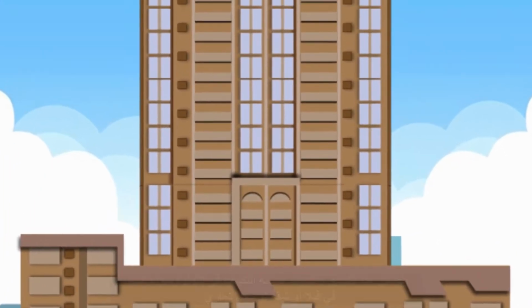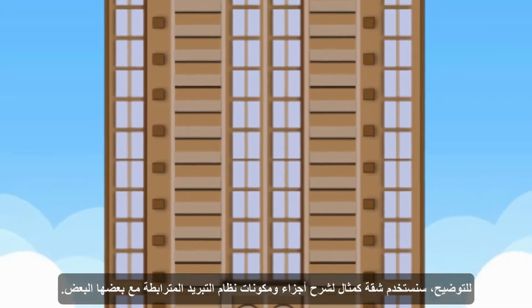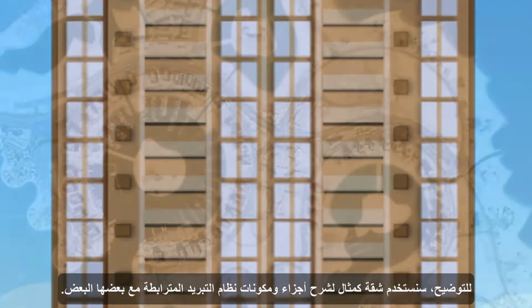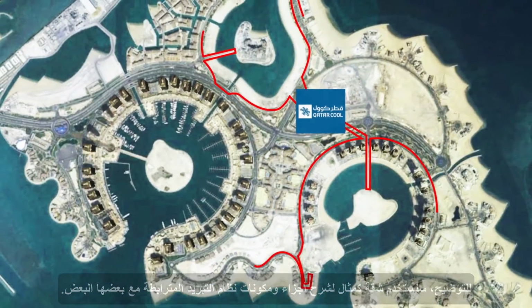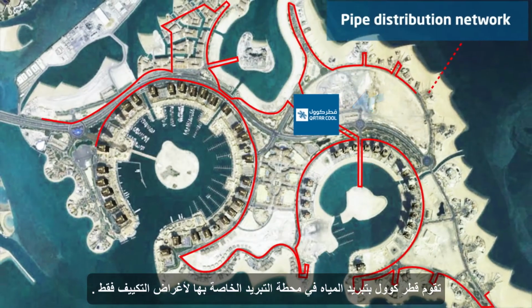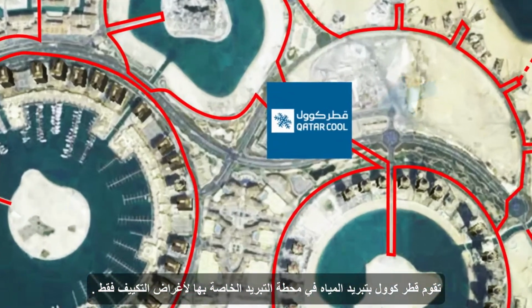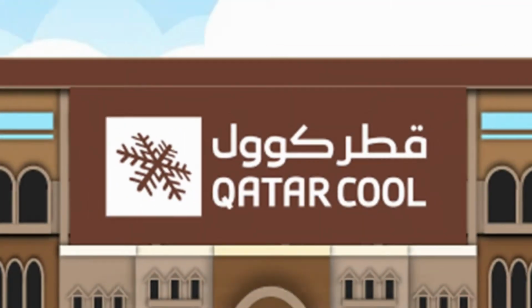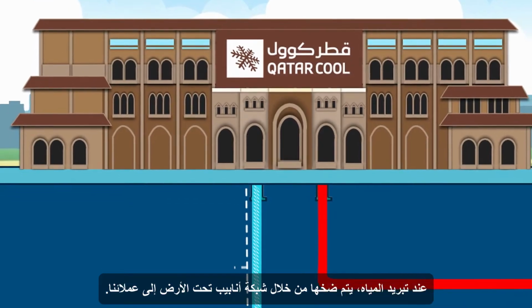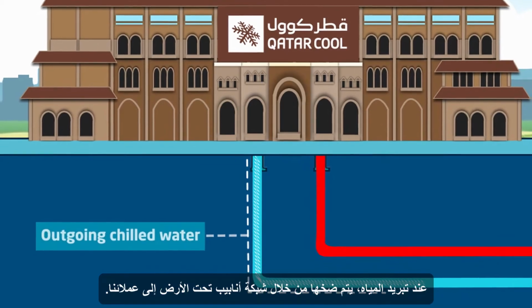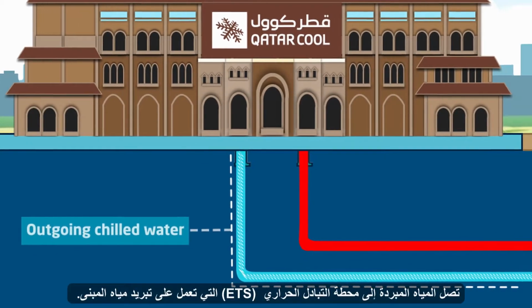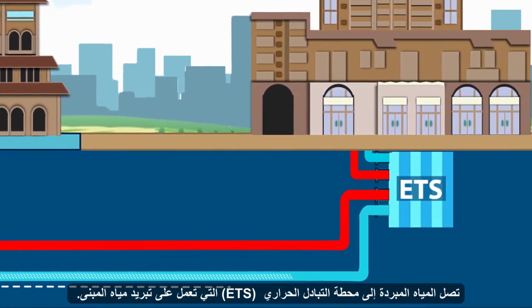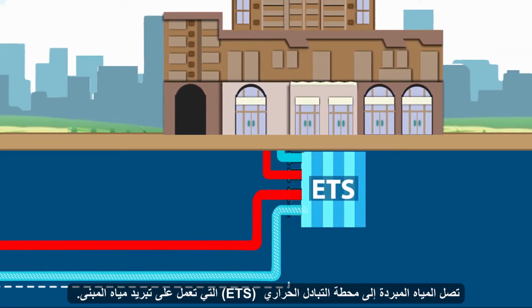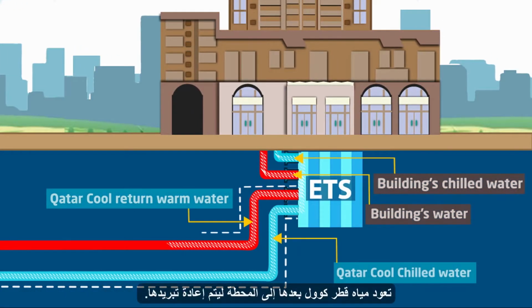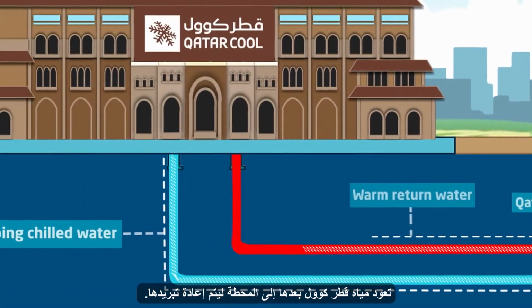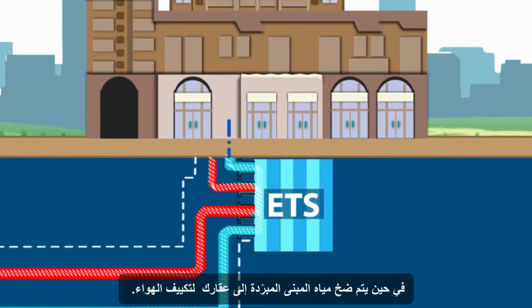property types. For the purpose of this video, we will use an apartment to show the different features associated with your cooling system. Qatar Cool produces chilled water in our cooling plant for air conditioning purposes only. Once the water is chilled, it is pumped through an underground pipe network to our customers. The water reaches a machine called an Energy Transfer Station, ETS, where the water chills your building's water.